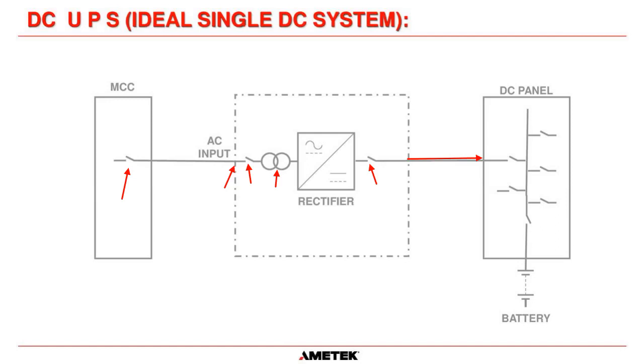Now, there are many systems out there that aren't designed as well as they should be, but you should always have a means of disconnecting the charger from the DC panel. So you should have a breaker specifically for your charger. Now, that could be the main breaker for the DC panel or a separate breaker for the DC panel, depending on the rating that's required. And then you will also have either a disconnect or a breaker for the battery as well, and you'll have your battery out here.